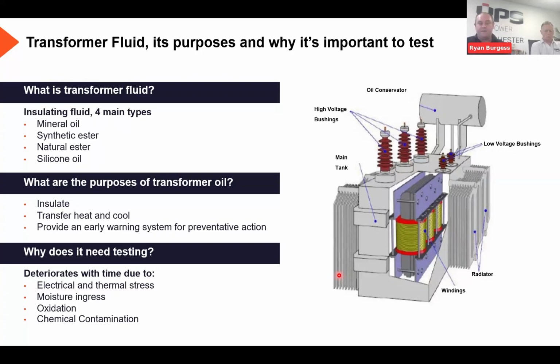And finally, it's a great preventative tool, just like a blood test. By testing it, we can determine what's going on with the oil and the asset itself. So why does it need testing? From the testing, we can determine what type of faults are happening. So if there are electrical or thermal stresses within the transformer, and as the oil degrades, those cooling and insulating properties are reduced. So by testing, we can monitor them over time to see if they're still effective or if they are deteriorating. And that's ultimately what we're here for.